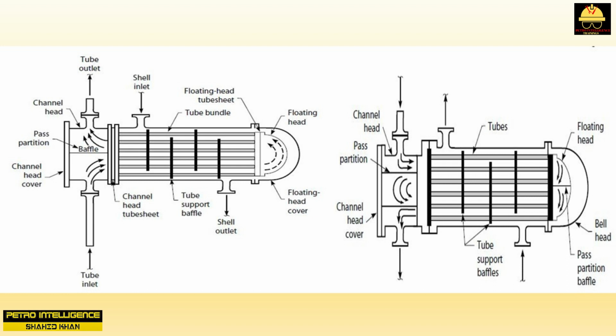For a new center pass partition baffle is welded in the floating head. The floating head tube sheet must also be remachined. The resulting 4-pass tube bundle will have a tube side velocity twice as high as it did when it was a 2-pass exchanger, 3 feet per second. Experience has shown that in many services, doubling this velocity may reduce fouling rates by an order of magnitude.